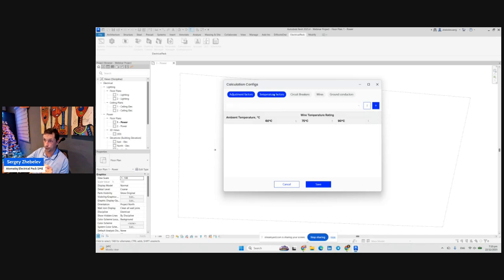Then temperature factor: again, as ambient temperature goes up, the wire's final ampacity goes down, and vice versa. When ambient temperature goes down, we have better conditions for our wires and they can carry more current. Here you can set up ambient temperature and ratings; for the default template it's grayed out, but you can make these temperature factors work.